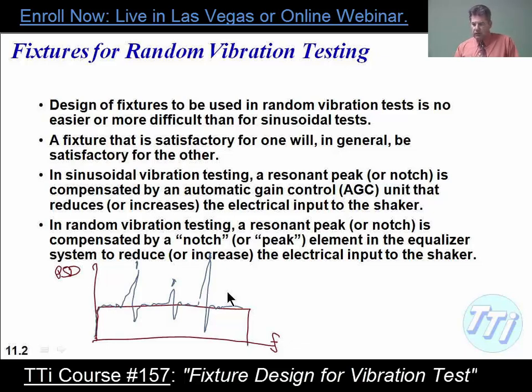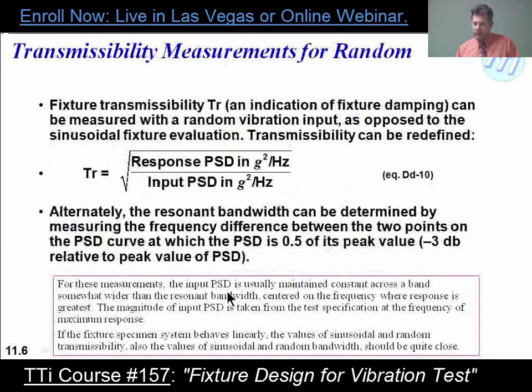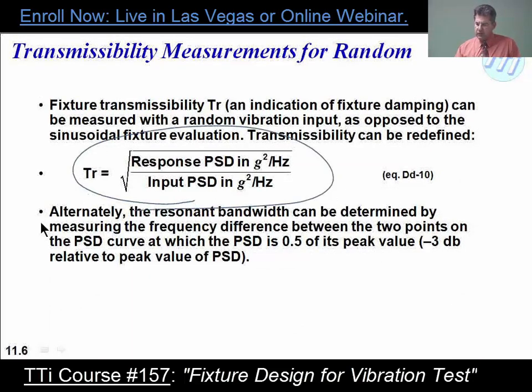In general, a fixture that works for random will generally work for sine. If you measure the response power spectral density compared to the input power spectral density in G squared per hertz and take the square root, that will get you the transmissibility.